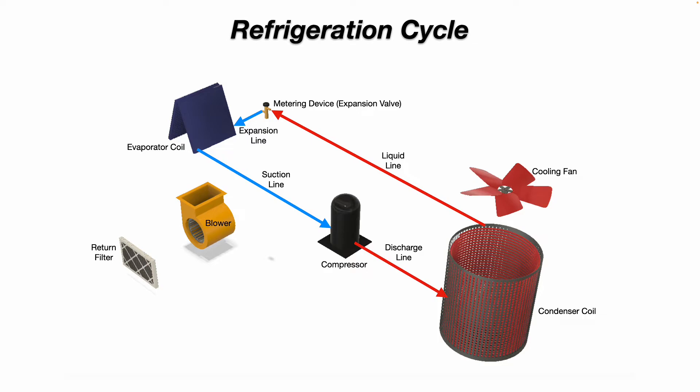It leaves the metering device as a lower-pressure, lower-temperature liquid with some flash gas on the expansion line going into the evaporator coil. Inside the evaporator coil, the refrigerant will change state again from a liquid to a vapor. It then leaves on the suction line as a cool vapor going back to the compressor. That cool vapor refrigerant also acts as a coolant to keep the compressor motor windings from overheating.